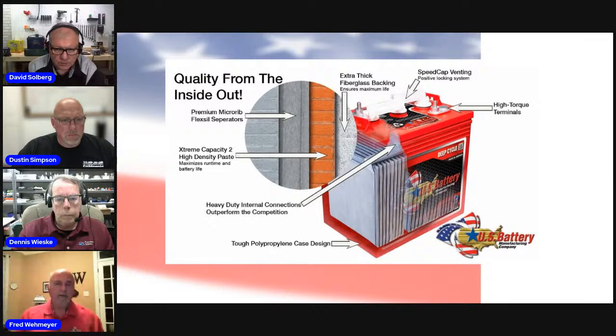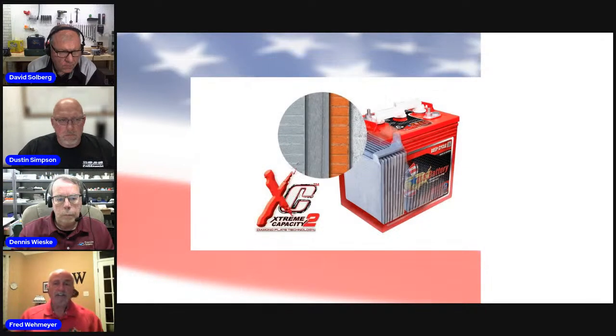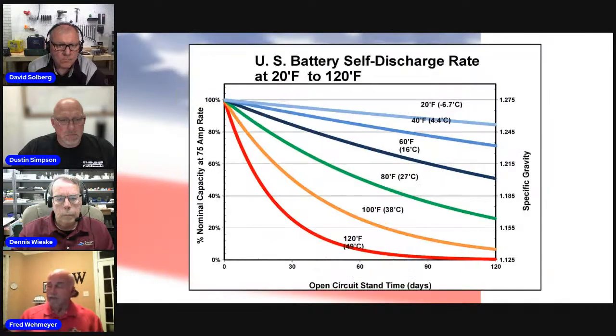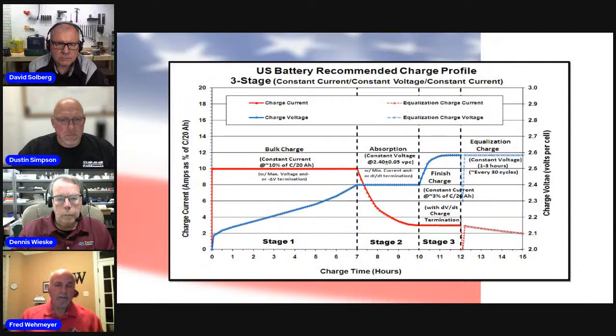Deep cycle batteries do have slightly different performance characteristics. They have the desirable characteristic of long cycle life. A premium deep cycle battery should last 500 to 700 cycles if you discharge it completely on every discharge. Another characteristic is that if you manage the depth of discharge, you can get a much longer cycle life.